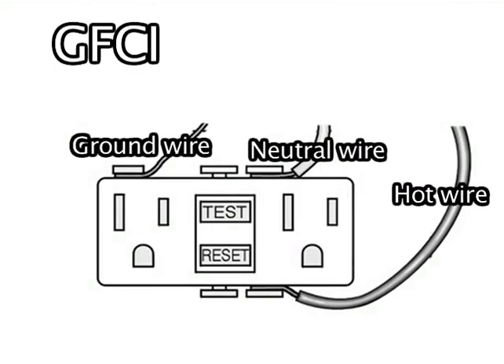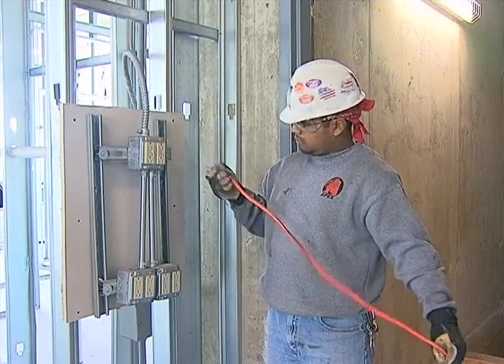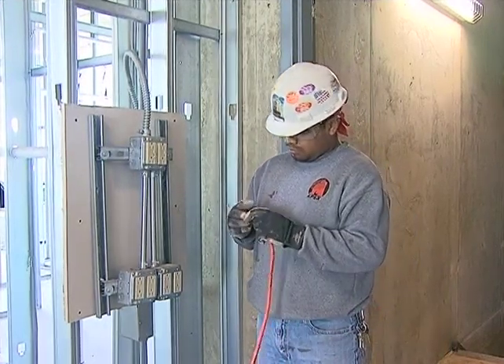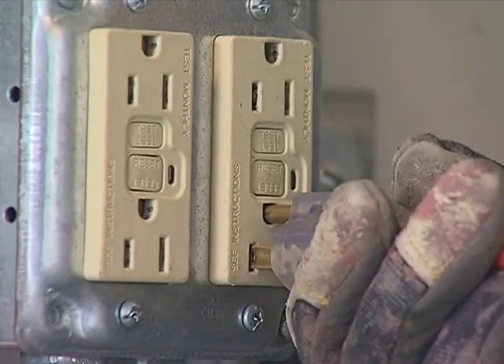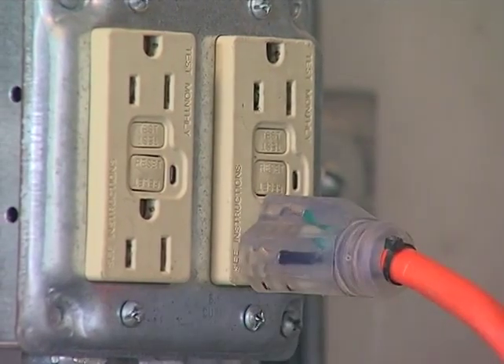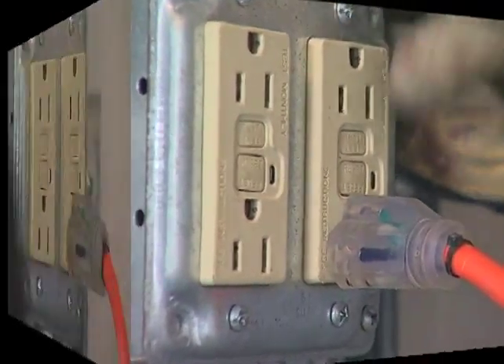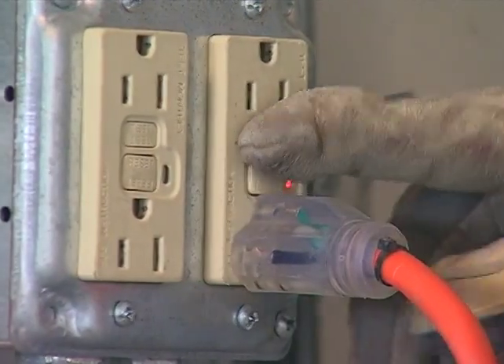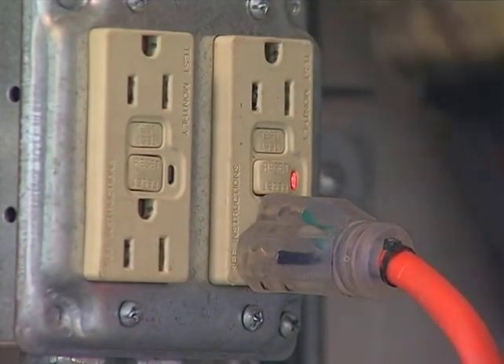A GFCI works by comparing the amount of current going to and returning from equipment along the circuit conductors. When the amount differs by approximately 5 milliamperes, the GFCI interrupts the current, shutting down the equipment.